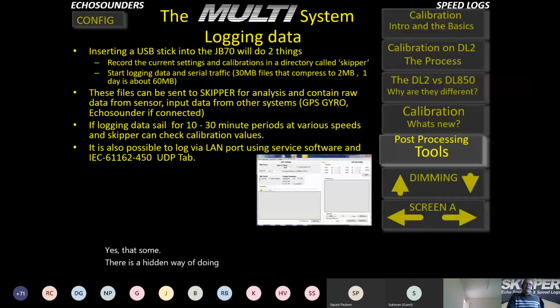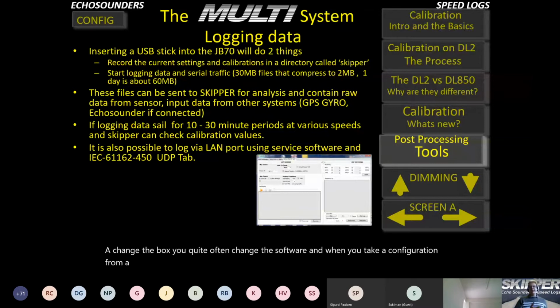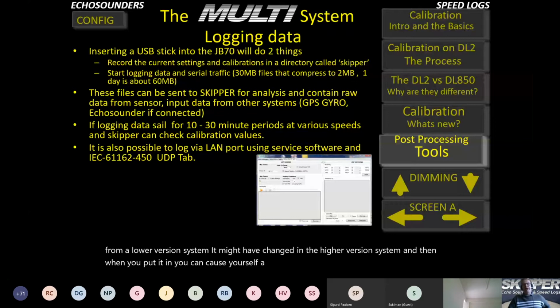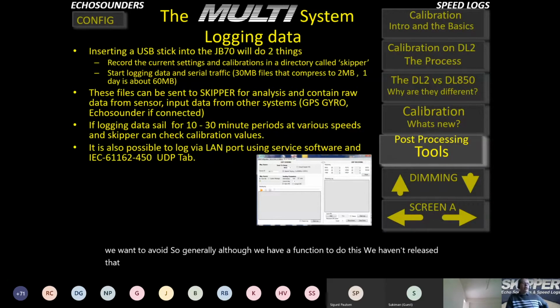The reason we haven't released this very much is because when you change the box, you quite often change the software. And when you take a configuration from a lower version system, it might have changed in the higher version system. And then when you put it in, you can cause yourself a little crash on the system, and that is something we want to avoid. So generally, although we have a function to do this, we haven't released that because we don't want to cause more problems than it's worth.